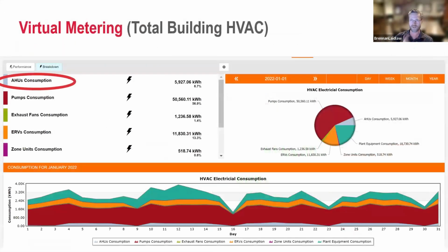Taking a little step back now, what does that mean for energy? One of the techniques you can do is taking all that data from your building automation system, all that motor data, all that functional data, and apply calculations to it. It's an example of a building automation system that ran all of the mechanical system in a building. We looked at every single fan, motor, and horsepower, and we calculated all the motor loads based on that data, using energy calculations in combination with nameplate data.